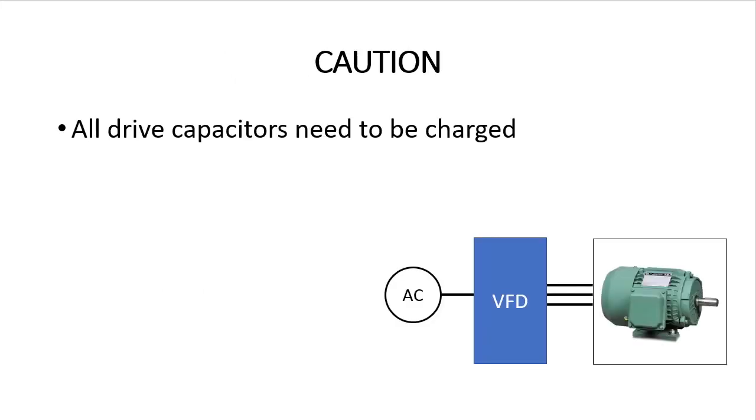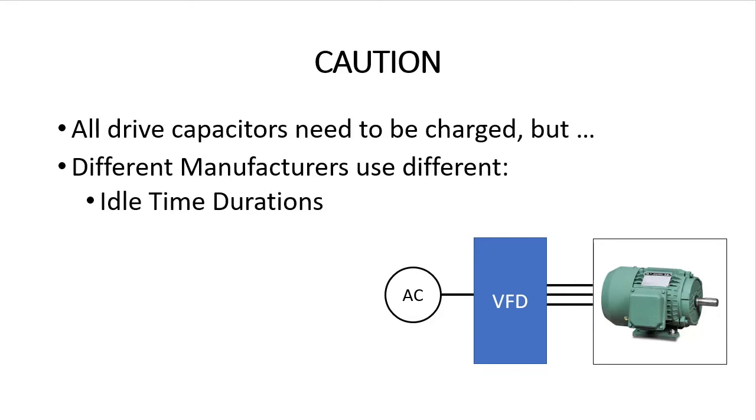All drives have these big electrolytic capacitors and they all need to be recharged or reformed if they have been idle for a while. But beware that how long the drive has been sitting idle and exactly what the recharging procedure is varies depending on drive manufacturer.